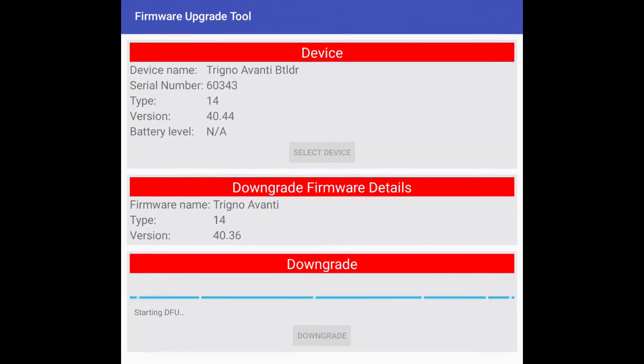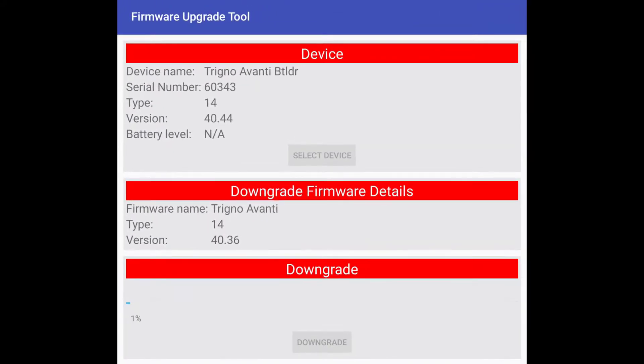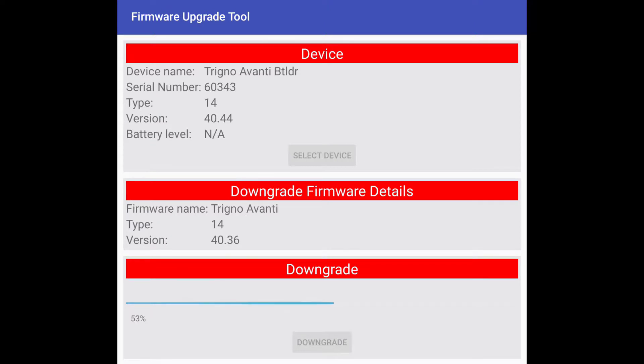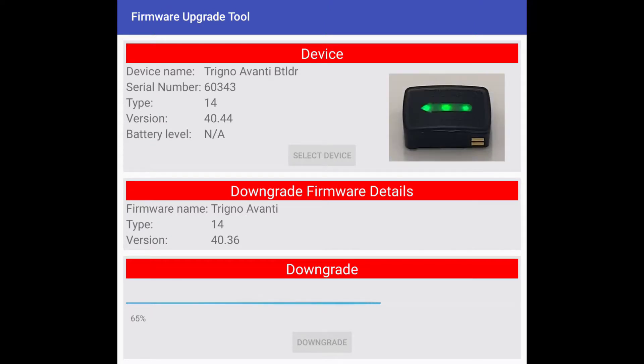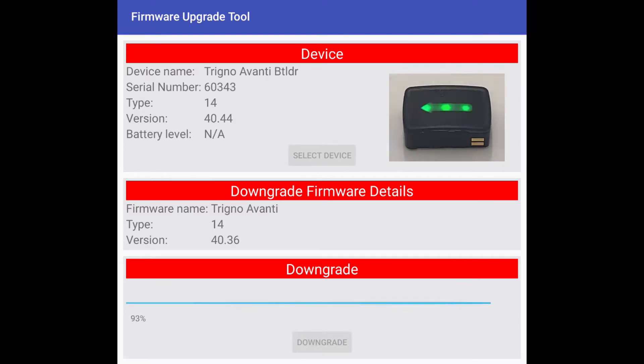While downgrading, do not return the sensors to the dock and do not close out of the firmware update application. This process may take several minutes to complete. Note that the sensor will flash green when the update starts, magenta and blue during the update, and green when finished.